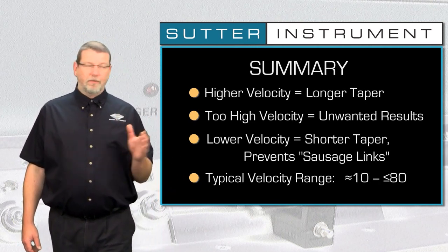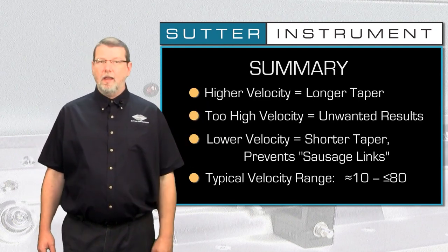Don't just simply use the 55 from our example today across different pipette styles and for different types of glass. The typical range for your average patch, micro or injection pipette is between 10 and 80, but where in that range the optimum lies, that will vary.